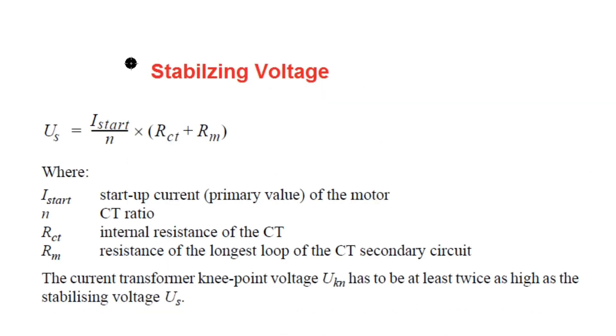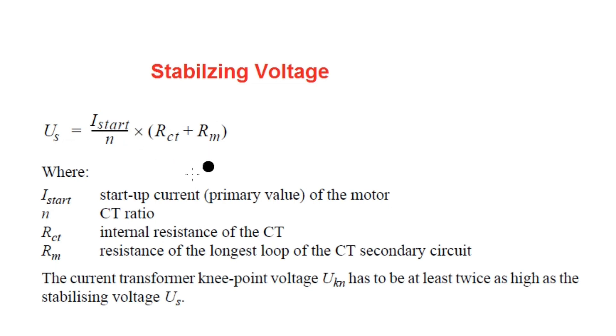To calculate the stabilizing resistance connected in series with the relay, we first calculate the stabilizing voltage Us, given by the formula: Us = (Istart / n) × (RCT + Rm), where Istart is the starting current in primary value, n is the CT ratio, RCT is the CT internal resistance in ohms, and Rm is the resistance of the longest loop of the CT secondary circuit.